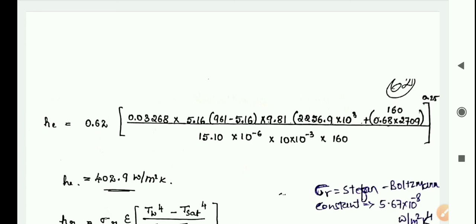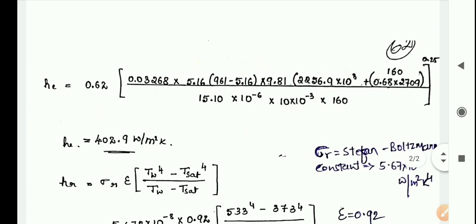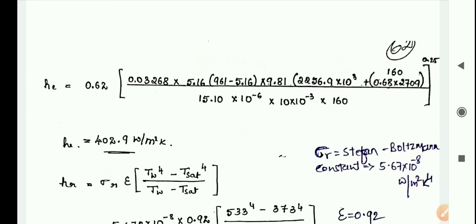...in the bracket, k cube times rho v times (rho L minus rho v) times g, in the bracket hfg plus 0.68 CPv times delta T, divided by mu times D times delta T, whole raised to 0.25. This formula is available on page 143. Substituting all the values, the hc value is 408.9 Watt per meter square Kelvin.